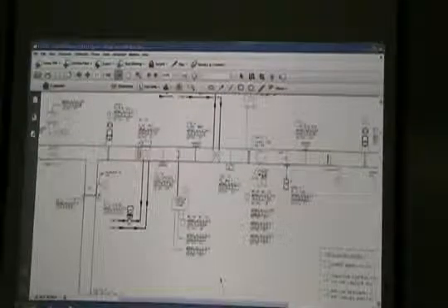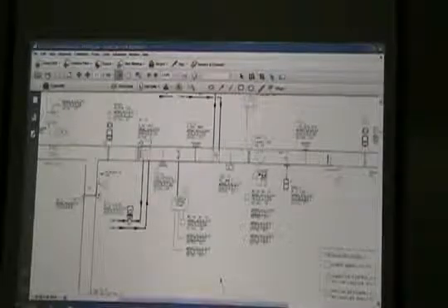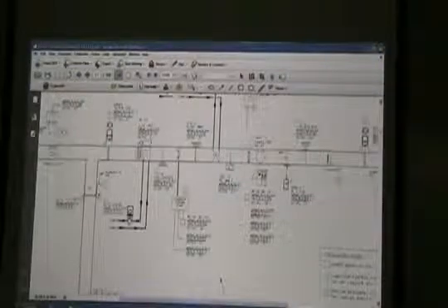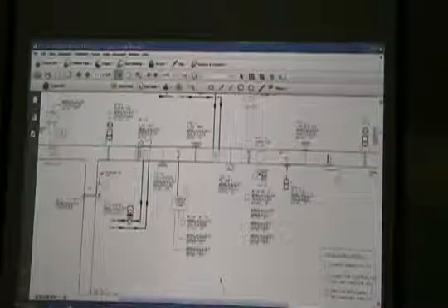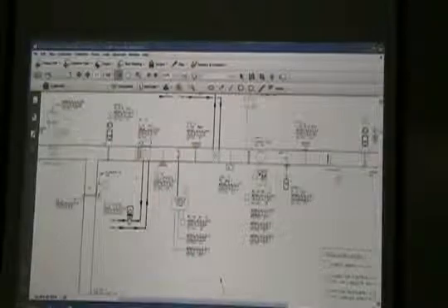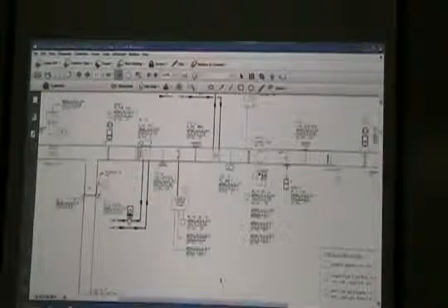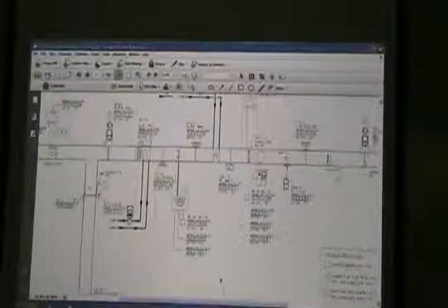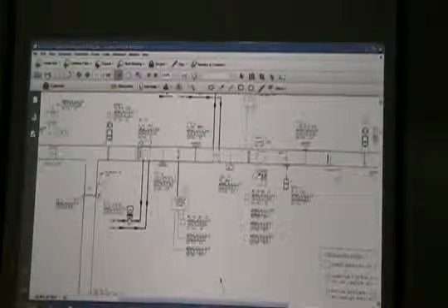In the event of a temperature low limit alarm, the preheat valve should be fully open to the coil, and base bypass should be fully open to the coil. Read that again. In the event of a temperature low limit alarm, the preheat valve shall be fully open to the coil, and the base bypass dampers shall be full open to the coil. Meaning that we're not getting enough flow to heat the air, so we want to go all air through the coil, no air through the bypass.